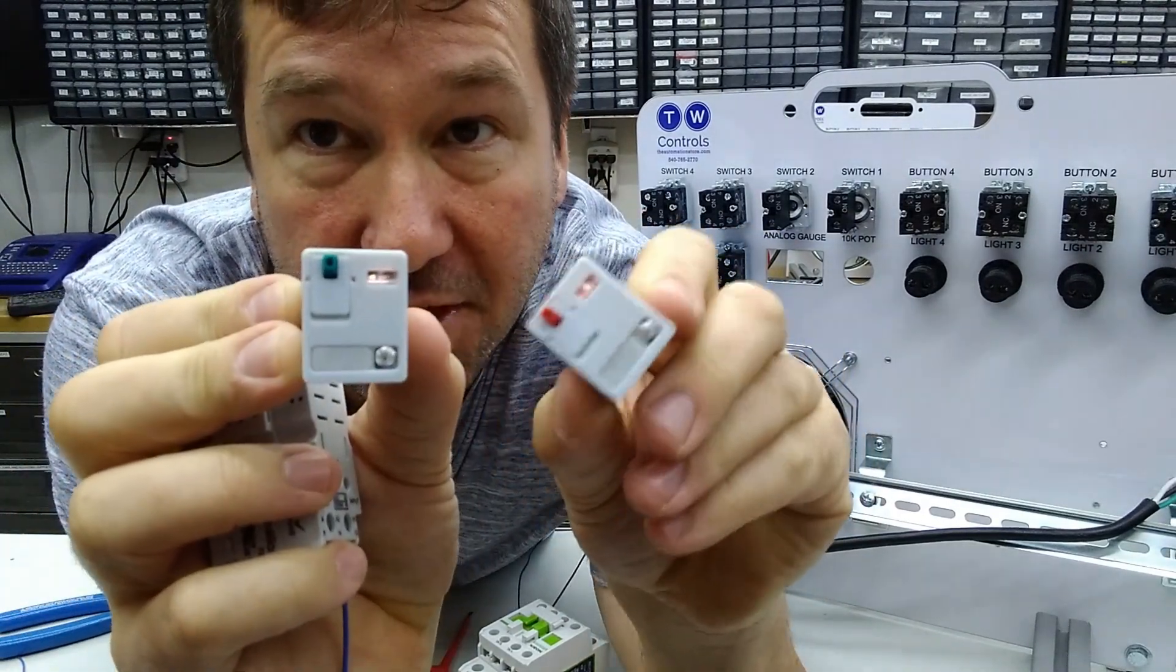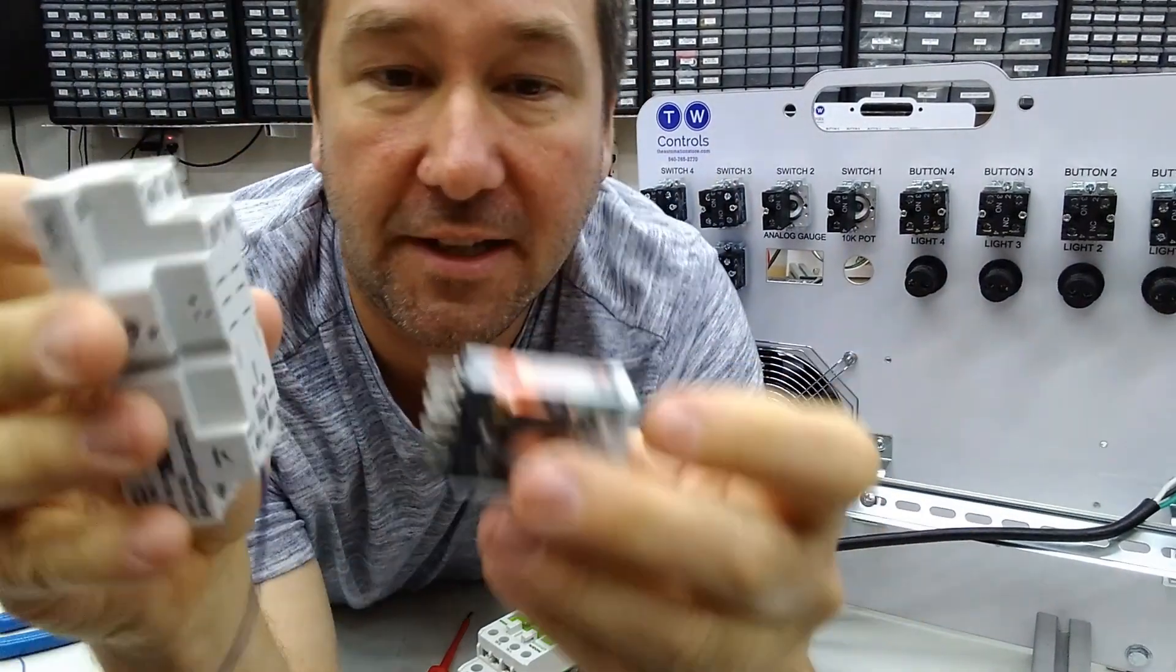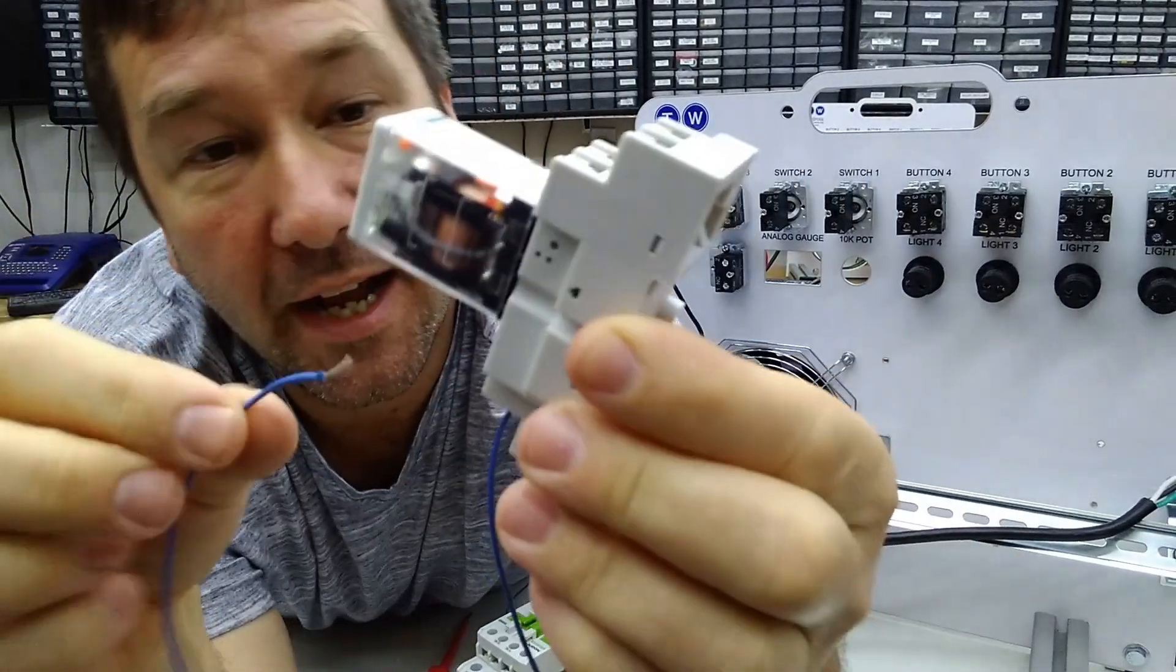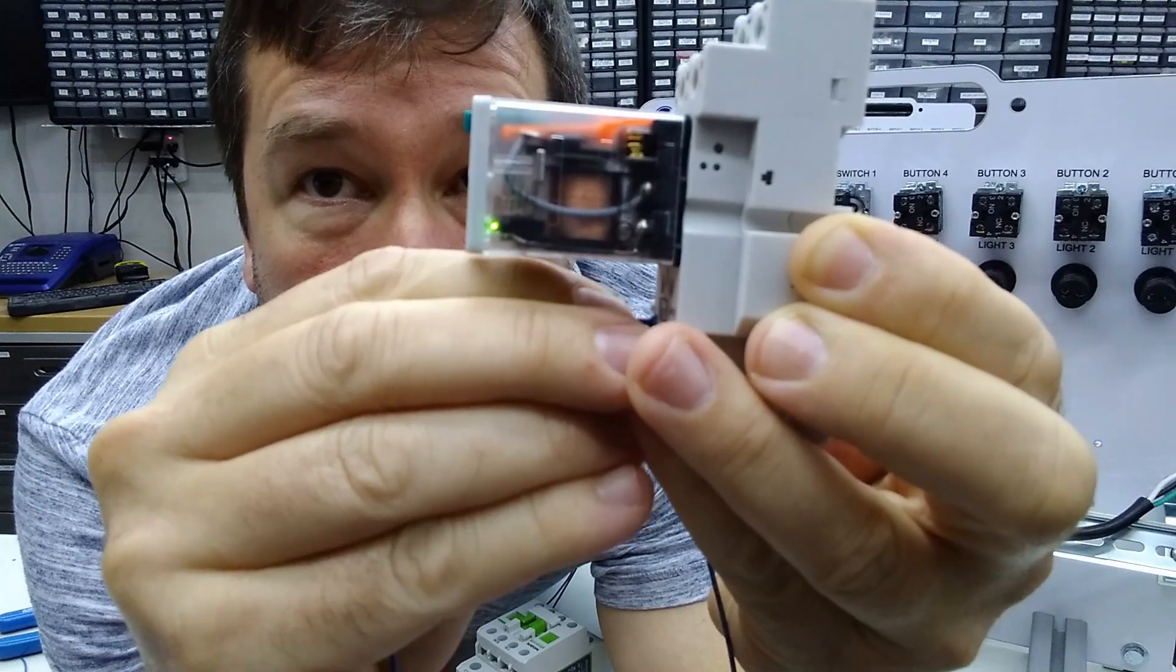We're going to take that off and we will snag this 24 volt relay. Now note, these relays really look physically the same. In fact, besides that red mark on the front of the 220, you can't really tell the difference. You'll need to look really closely at the ratings of relays to see them. And now it'll slide right into the same socket bit. And we'll try it again. So now I'm going to touch it. And there it is. You can see it physically moving up and down. And that is what's happening inside all of your relays and your contactors.